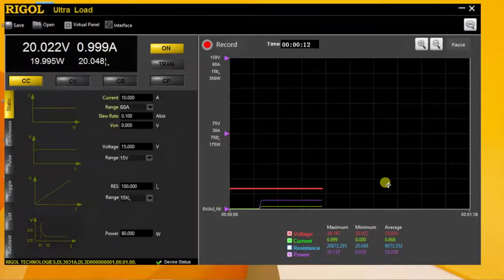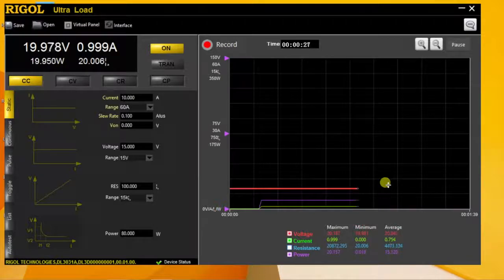So this battery test will stop when it's over and we'll have a complete time set of data including voltage, current, power and resistance for all the points during that test. This is a great way to record your data for later analysis in addition to anything you might do visually on the front screen.